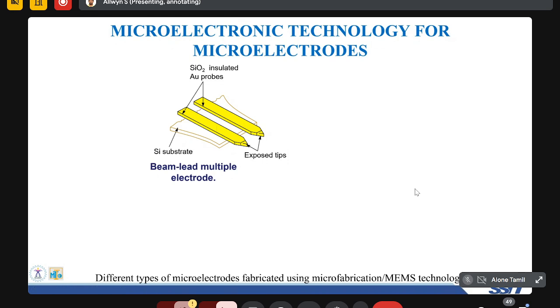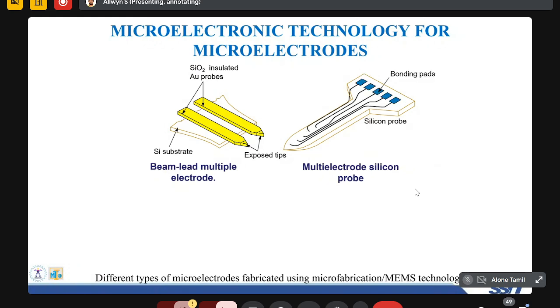This is usually used for multi-site neural or tissue recording with high spatial resolution. For that purpose, this type of beam-lead multiple electrode is used. The next one is the multi-electrode silicon probe. In the same way, this also has a silicon base, a silicon probe, and the silicon shank has bonding pads and connectors. These connect to amplifiers, and it also has gold-coated, gold-exposed electrodes. This is also ideal for deep brain recording and multi-neuron studies.